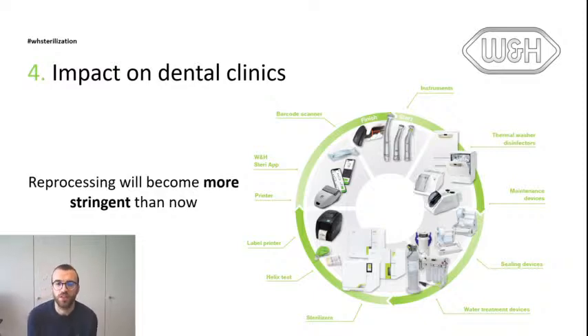Another aspect is the water, which in many cases is not really considered in the workflow, but it's really important, because in sterilization and also in cleaning, the use of distilled water, high quality water, avoids some trouble on device reliability and also on instrument reliability. Because if the user, the dentist, uses water that is not correct, or not high quality, it can create pitting on the instrument, and maybe block small channels, for example inside the handpieces.